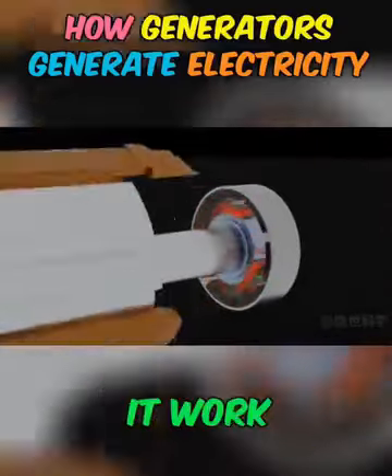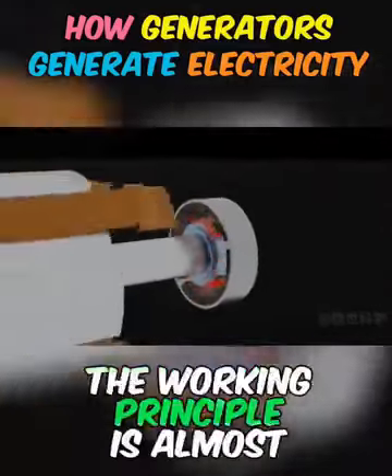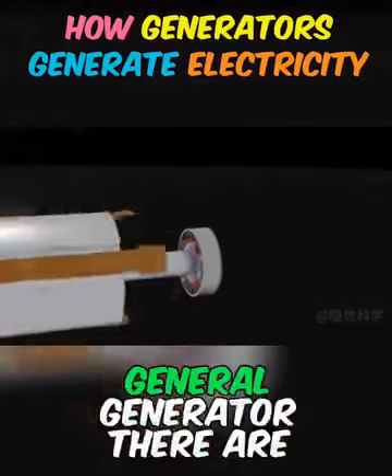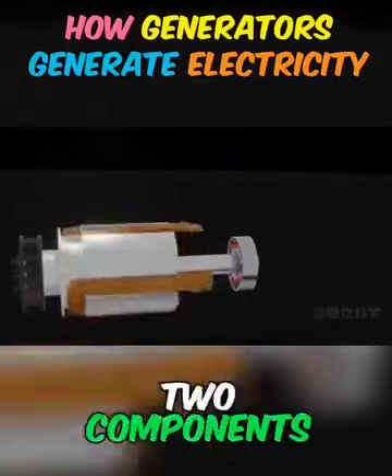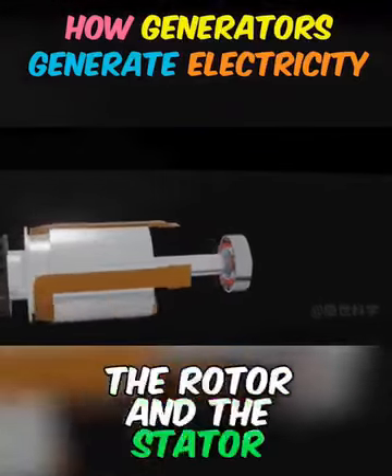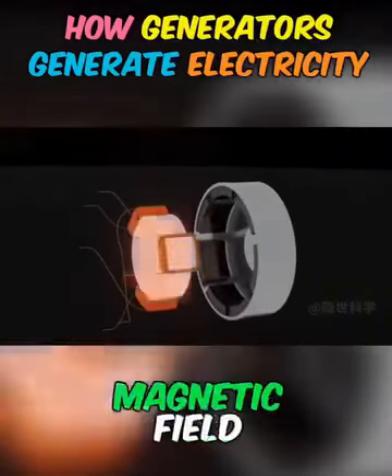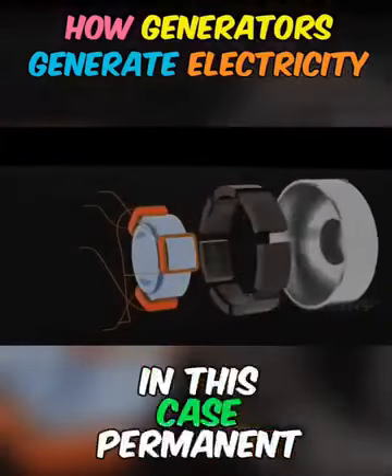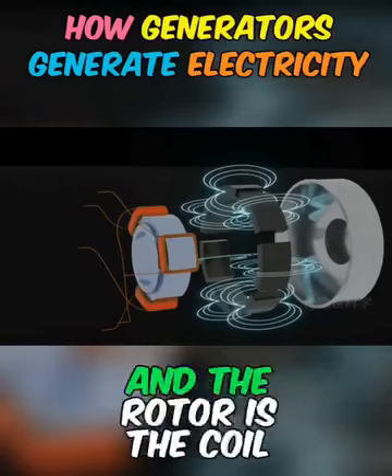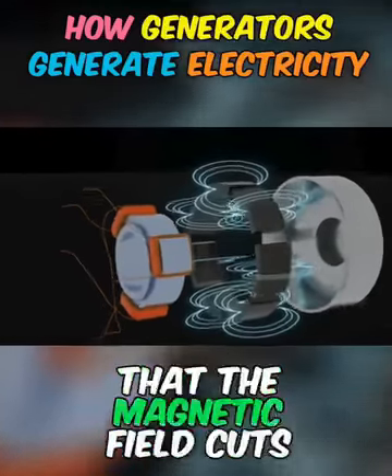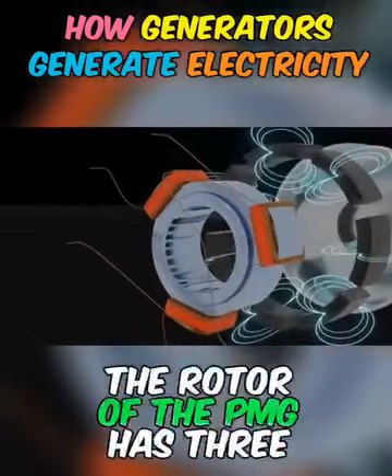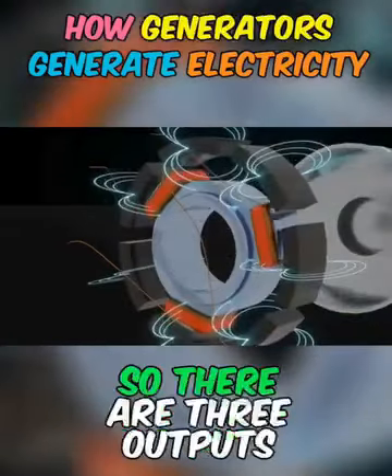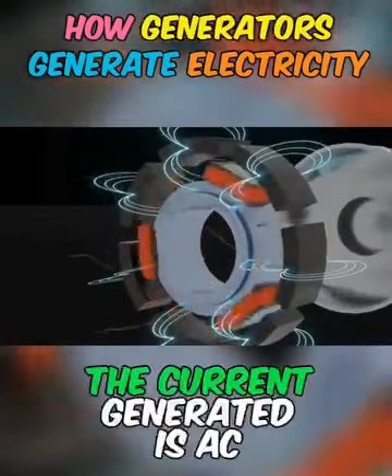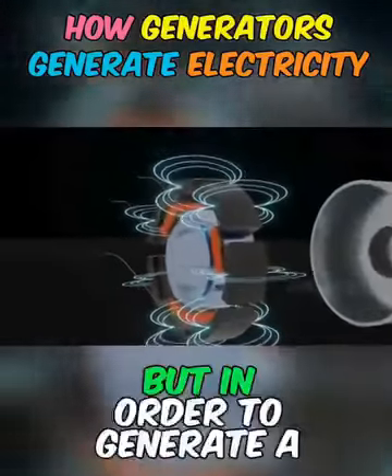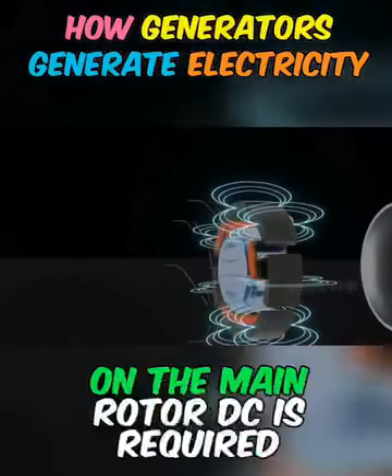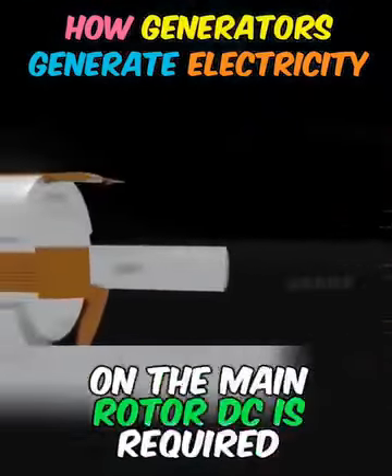So, how does it work? The working principle is almost the same as a general generator. There are two components, the rotor and the stator. The stator provides the magnetic field. In this case, permanent magnets are used, and the rotor is the coil that the magnetic field cuts. The rotor of the PMG has three, so there are three outputs. The current generated is AC, but in order to generate a magnetic field on the main rotor, DC is required.